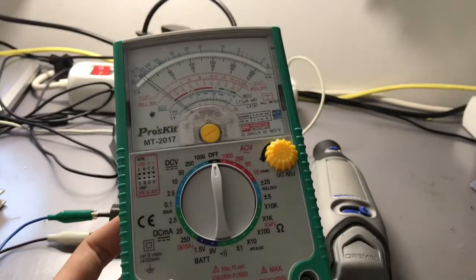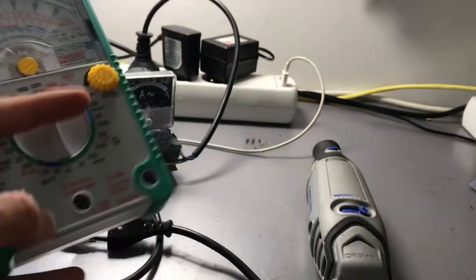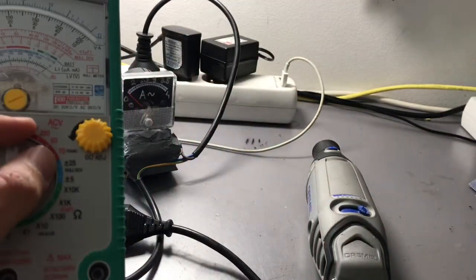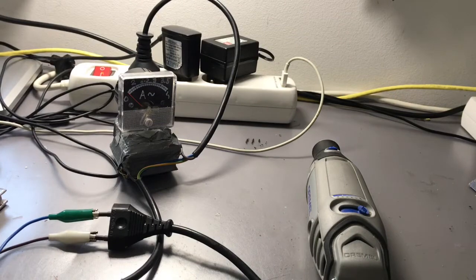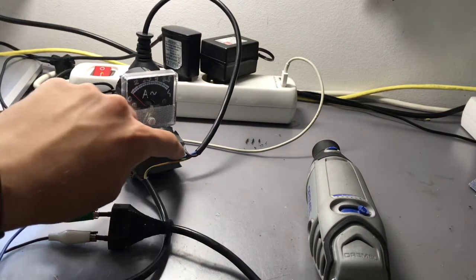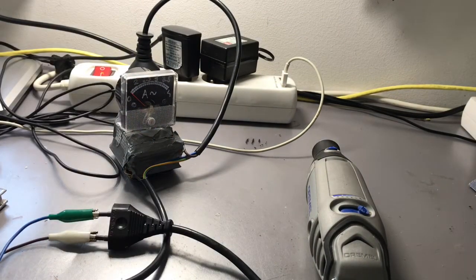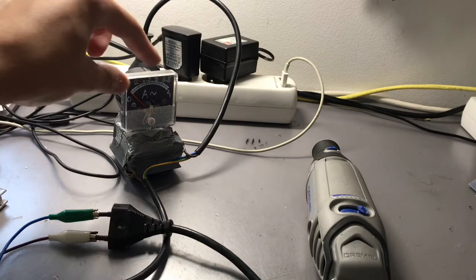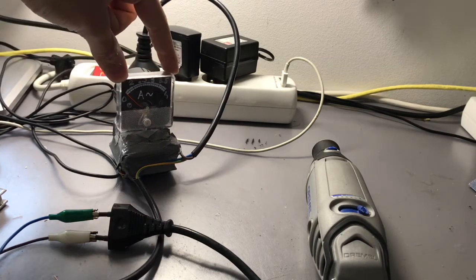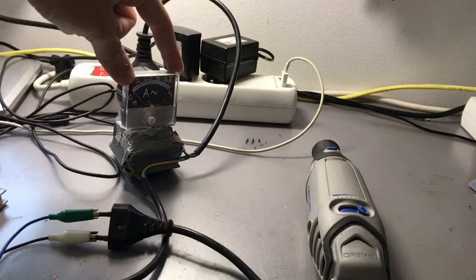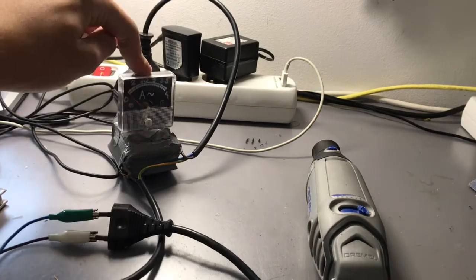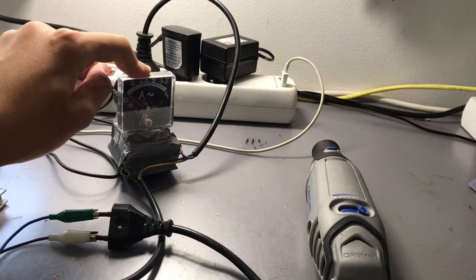I don't have any analog equipment that could do the same resolution, for example, because here I have 10 volt AC, and 10 volt AC across here would be like 100 amps or 10 amps. So that's too big, so I needed to calibrate a small movement to do it for me. And this is like the best accuracy you can get from this circuit.